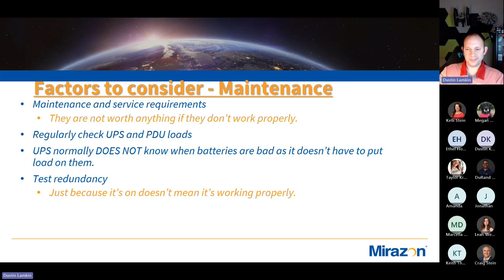And just like I said earlier, UPSs do not know when batteries are bad. We need to put load on them, stress test them, and see how they handle it. And test your redundancy - just because you have two PDUs doesn't mean they can both handle that load. So definitely test that out and make sure you're good.